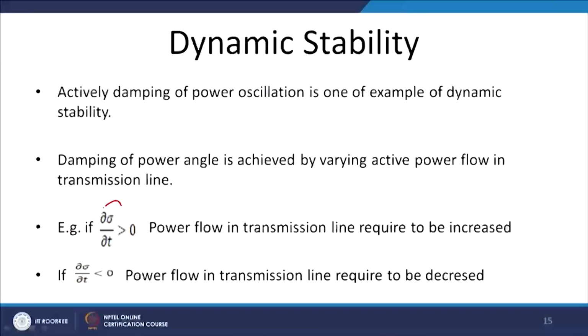If this term is positive, it means that power is increasing, and considering that delta is less than 90 degrees, in that case we need to increase the transmission line capability. Similarly, if it is less than 0, we need to decrease the transmission line capability, and by doing that we can actively damp out the dynamic oscillation and thus enhance the dynamic stability of the system.